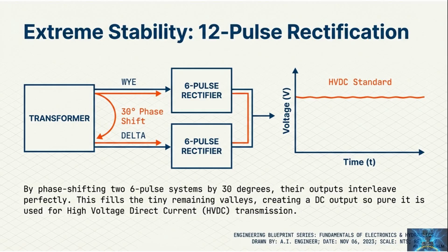12-pulse rectification, extreme stability. A 12-pulse system uses 2 6-pulse rectifiers fed through a transformer that phase shifts 1 by 30 degrees. Those outputs interleave, filling in the remaining valleys. The result is very low ripple and reduced harmonic issues compared to simpler rectifiers. This is why the concept shows up in high-voltage direct current transmission designs where efficiency and power quality are serious business.